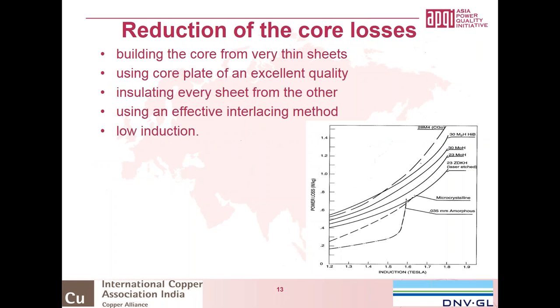How to reduce the losses of the core? Well, basically, if you want to reduce your eddy currents, try to make use of sheets which are very thin. But do know if you make them too thin, it will be very labor intensive because you have to build it per core. Also use core plate of an excellent quality. You can use, of course, the first iron that you'll see, but it's better to have an iron which already has a laser scratch, those kind of things. That will reduce definitely the losses within the transformer.